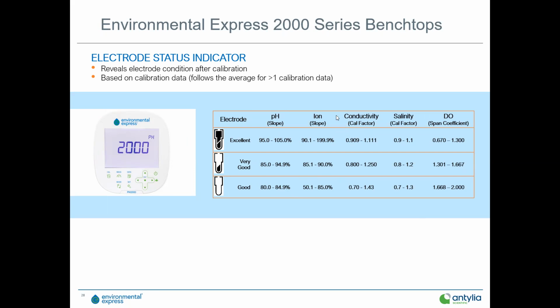Some of the other cool features on the ion meter, it also gives slope reading. The conductivity and salinity gives you a cal factor. So it tells you pretty much when you need to recalibrate the instrument, or in some cases, if you're going into an oxidizing solution and the plates on your conductivity cells start to oxidize, you may have to clean them and recalibrate. And then DO as well. Really cool feature that gives you some insight into what the sensor status is, whether it's pH, ion, electrical conductance, or DO.